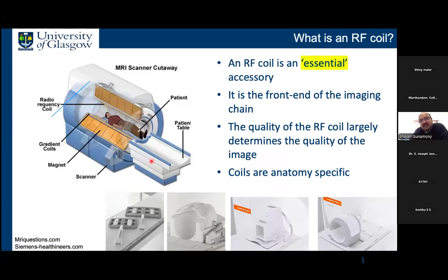If you have been to an MRI scan, you would notice that the nurse or the radiographer attach a device around the anatomy that they are planning to scan. So this device is basically an RF coil. It's an accessory, but it is an essential accessory because without an RF coil, you don't get an image. It's also the front end of the imaging chain, and it's really the first component that picks up the signal from the anatomy. So the quality of the RF coil largely determines the quality of the image.